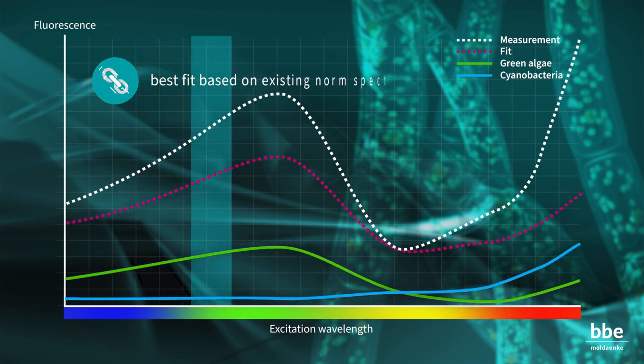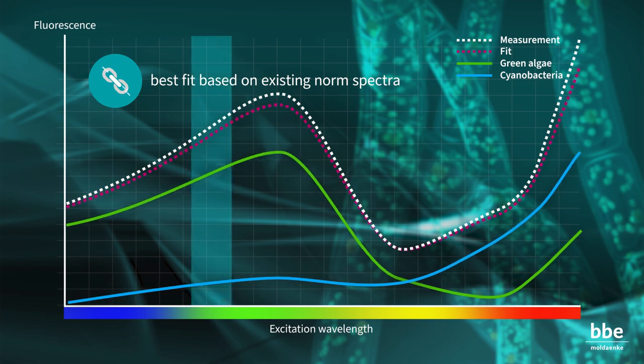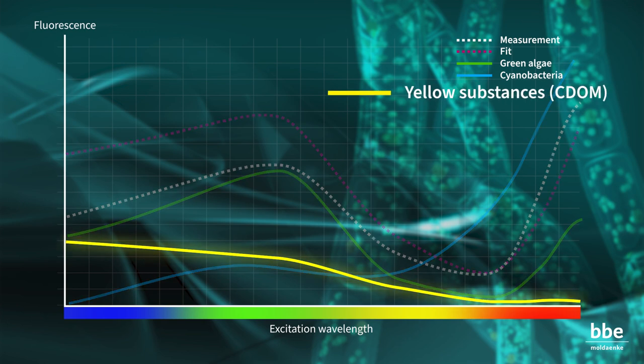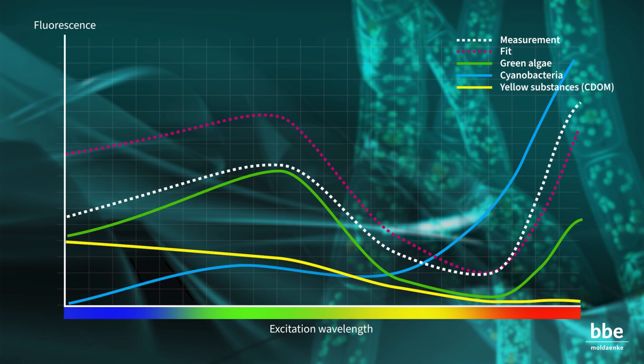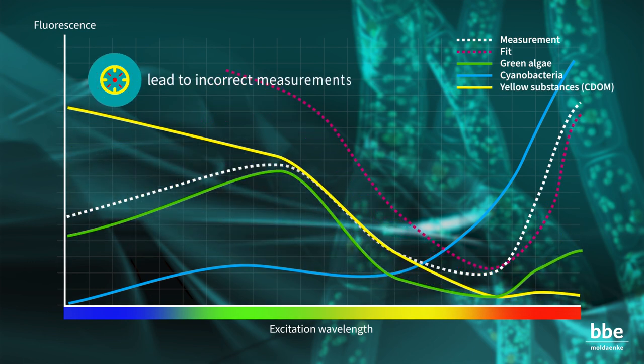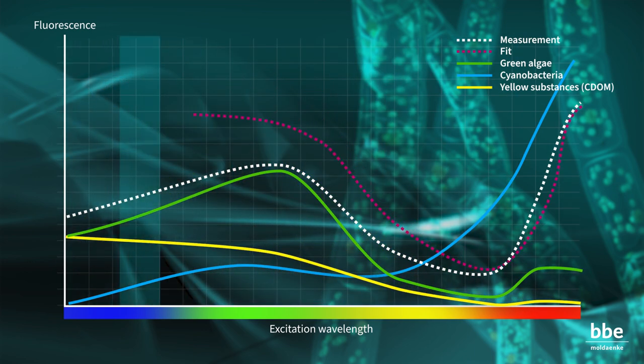Again, the software searches for the best match — in this case, the combination of two norm spectra. An important issue is the effect of so-called yellow substances, or colored dissolved organic matter. These compounds have interfering fluorescence effects and will lead to incorrect measurements. Knowing the fluorescence properties of yellow substances, the BBE devices compensate for their effects.